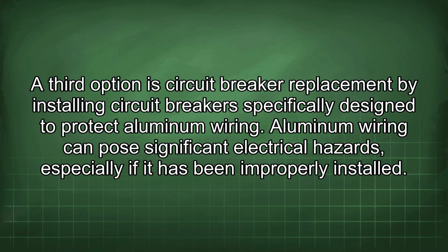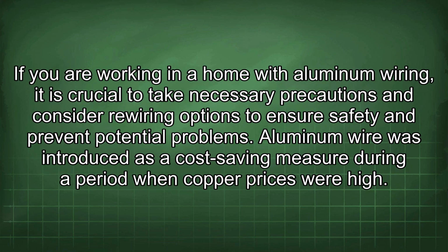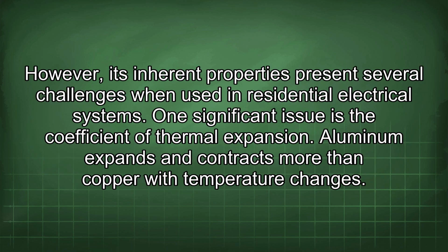A third option is circuit breaker replacement by installing circuit breakers specifically designed to protect aluminum wiring. Aluminum wiring can pose significant electrical hazards, especially if it has been improperly installed. If you are working in a home with aluminum wiring, it is crucial to take necessary precautions and consider rewiring options to ensure safety and prevent potential problems. Aluminum wire was introduced as a cost-saving measure during a period when copper prices were high. However, its inherent properties present several challenges when used in residential electrical systems.